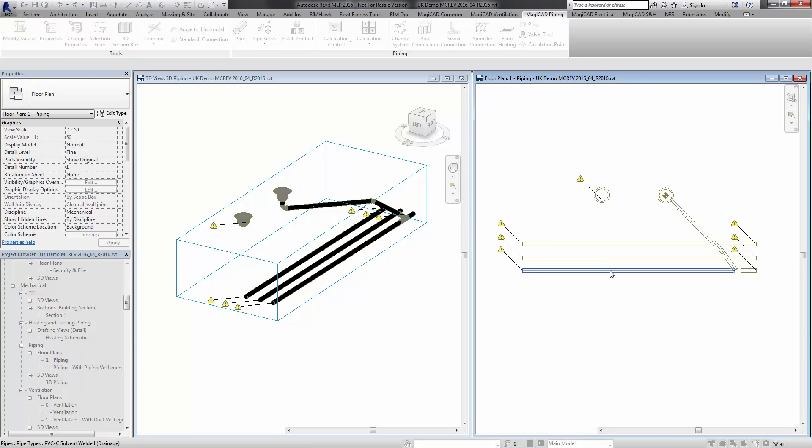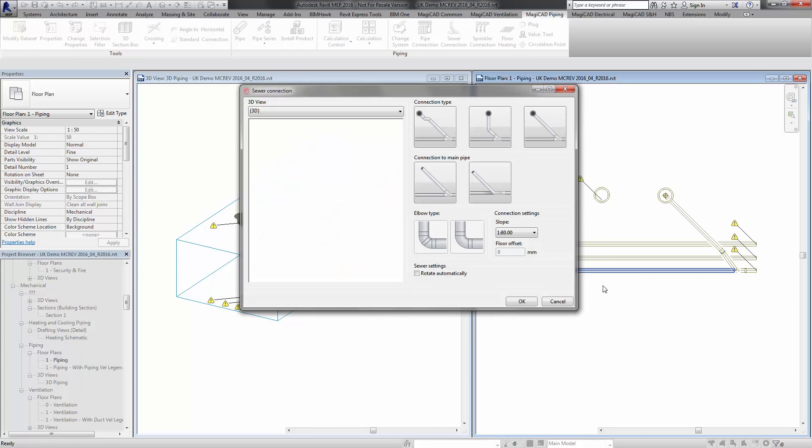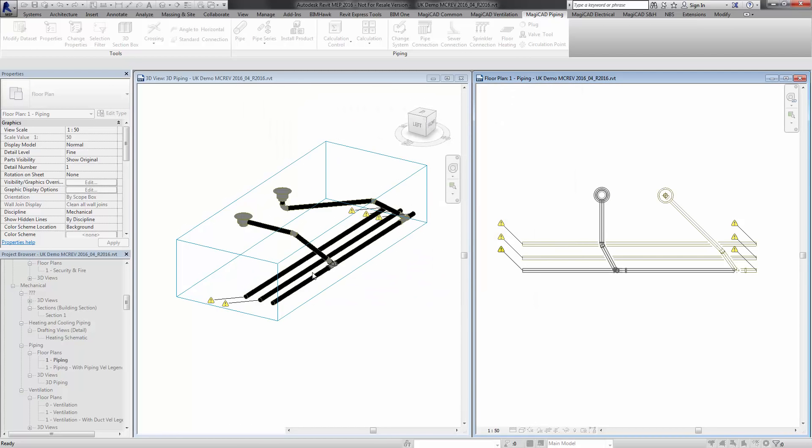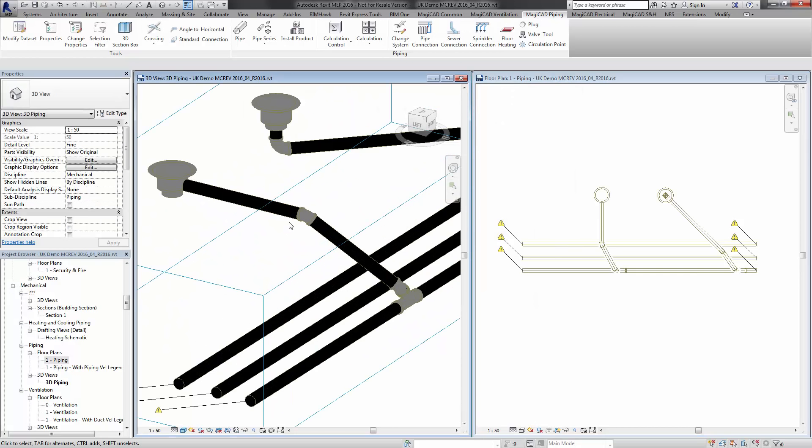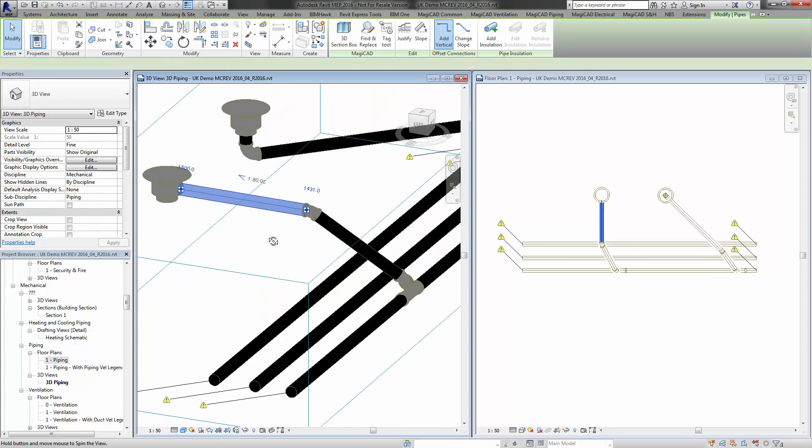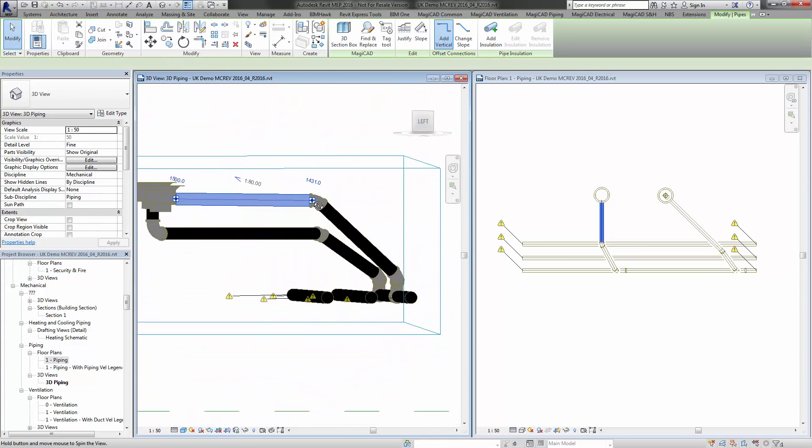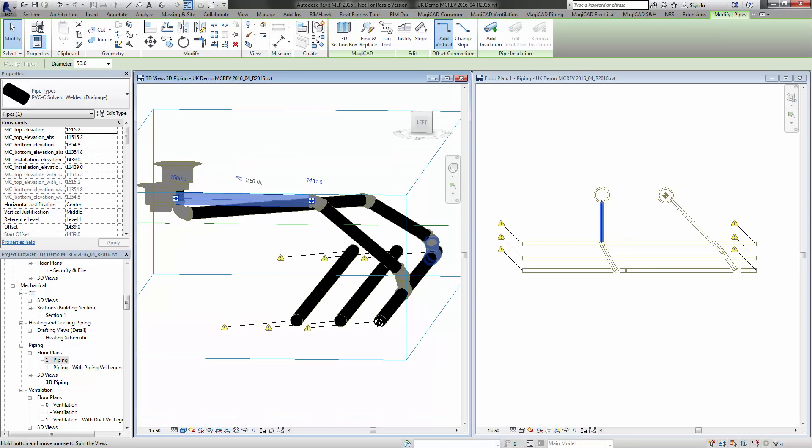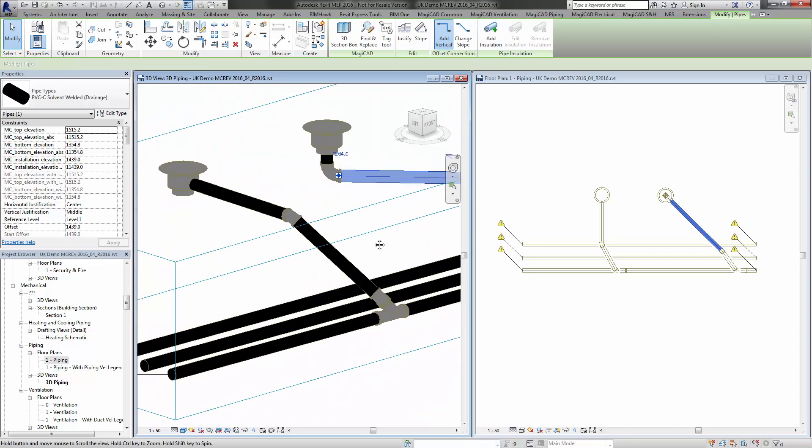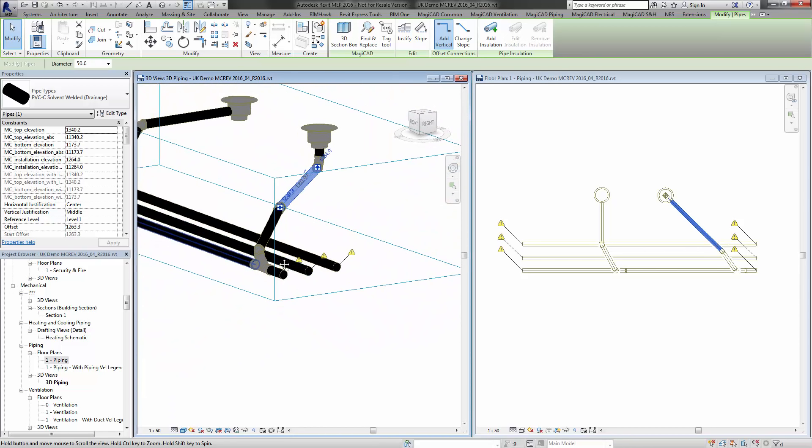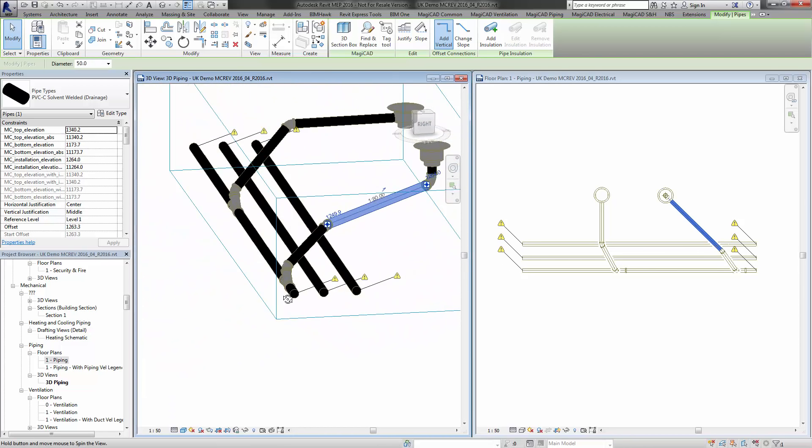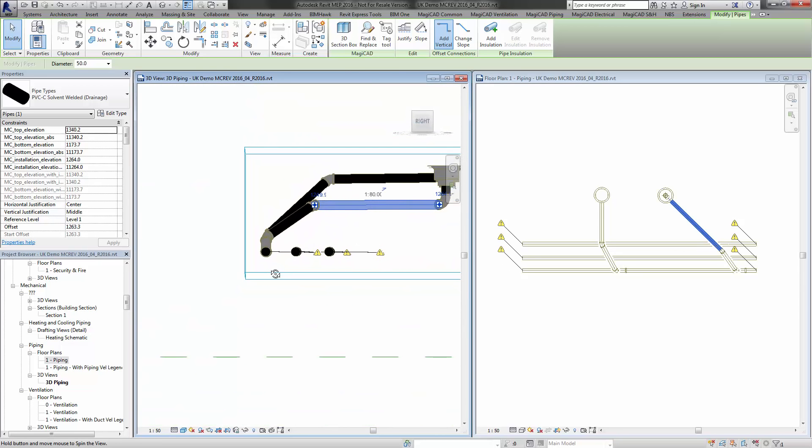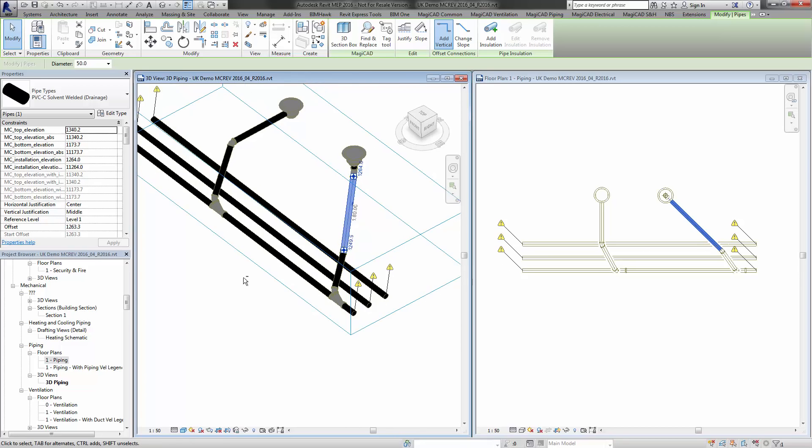Similarly, it will work with a gully in this case with a side connection, whereas the previous one was a vertical drop off the bottom. This one's now got a side connection. Press OK and you can see it's done the same thing. You can see in this view that we've now got perfectly vertical fittings, but then we come off at 1 in 80 and 1 in 80 as prescribed, and then the final drop to the connecting pipe is done in whatever angle it needs to be to ensure that connection is made.